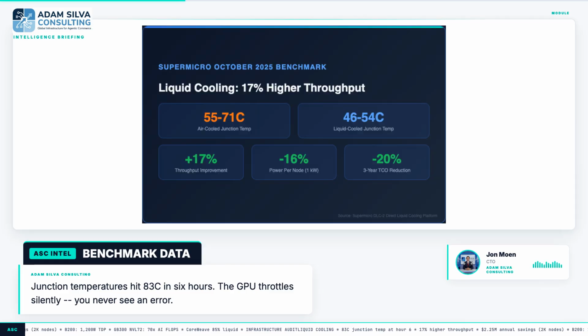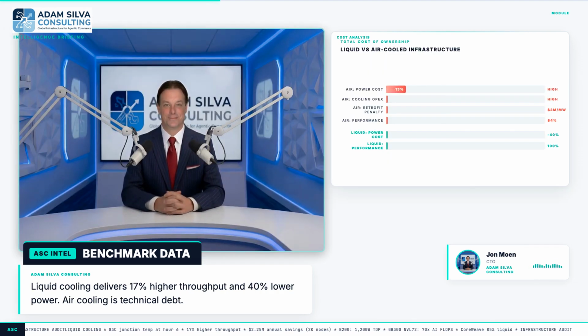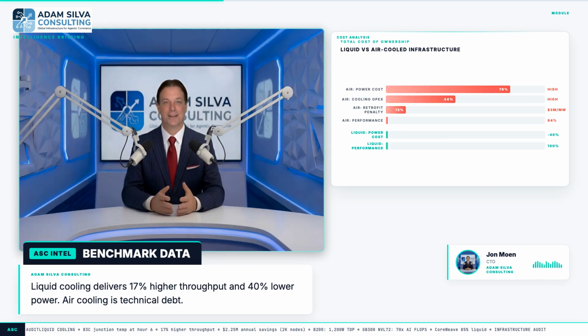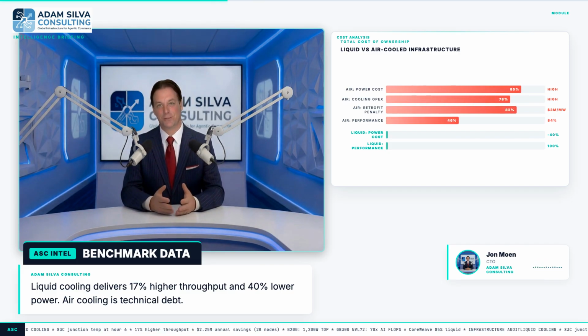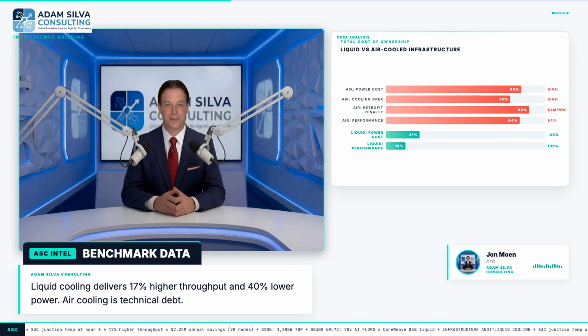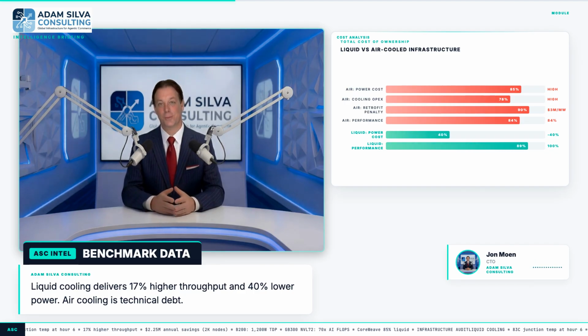I will wait. According to Supermicro's October 2025 benchmark study, liquid-cooled GPUs maintained 46 to 54 degrees Celsius junction temperatures versus 55 to 71 degrees for air-cooled equivalents under identical configurations. Under sustained stress tests, the liquid-cooled configuration delivered 17% higher throughput. Power consumption dropped by 1 kilowatt per node, a 16% reduction at 2,000 nodes. That is $2.25 million per year in electricity costs. At 5,000 nodes, $11.8 million.